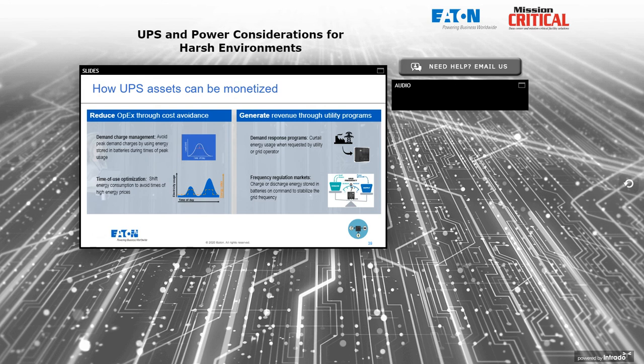Now, demand response, different than demand charge management, you see on the right-hand side of the slide here. Look at it from the utility company's perspective. They need to balance their demand on the hottest days of the year or the coldest days of the winter. And if they have a large UPS or a large bank of generators or a campus environment like a hospital that has 15 or 20 large UPSs with large battery banks, it can be aggregated together to act like one big UPS and battery resource. That allows them to actually be able to do things like balance their loading without having to kick on the other big power station or power generating station down the road.